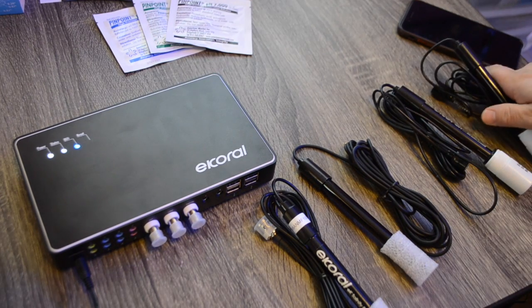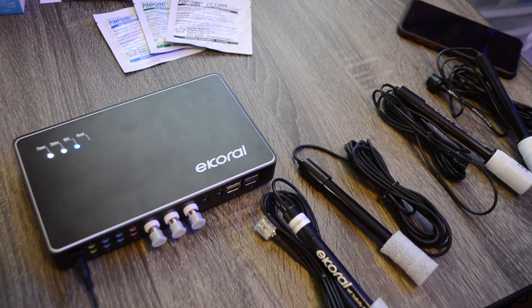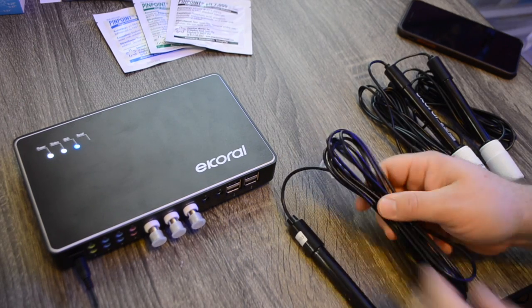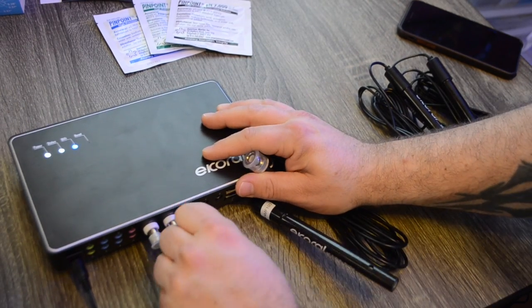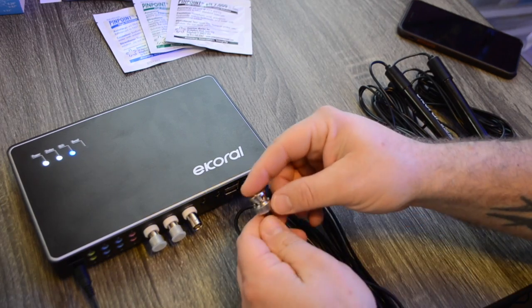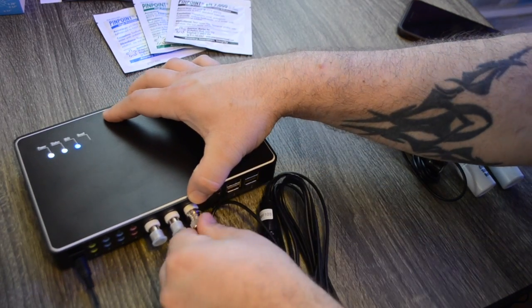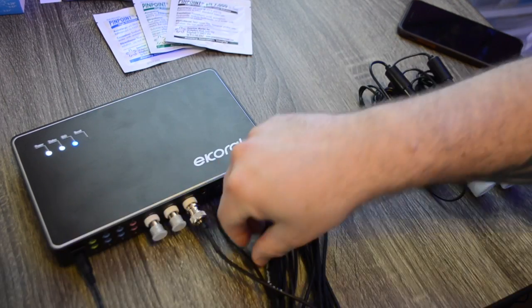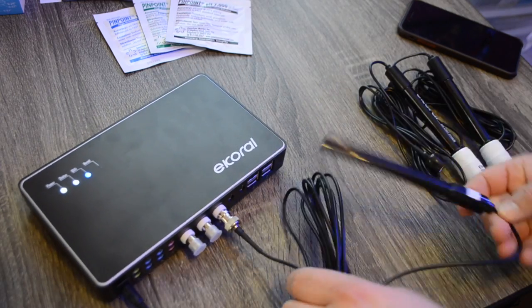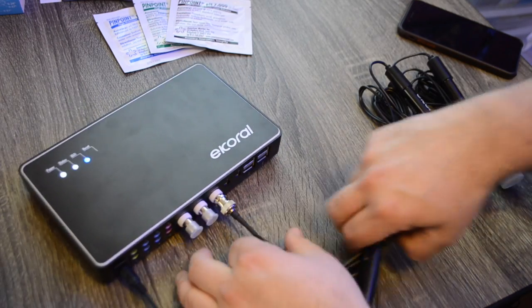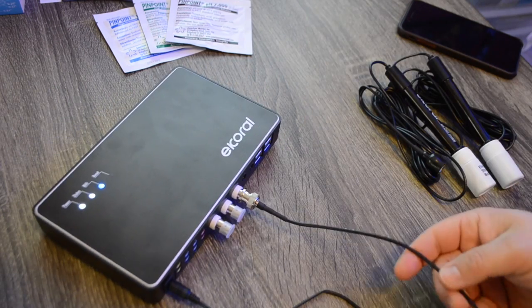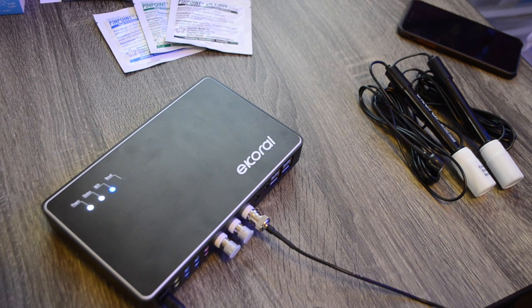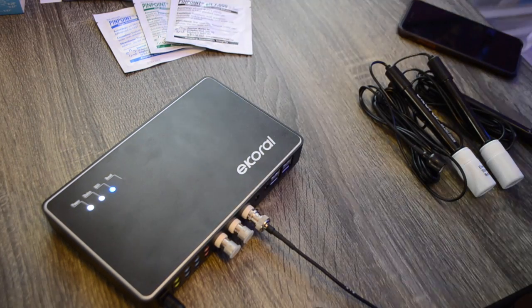When you turn your eKoral on for the very first time, it is going to prompt you to calibrate your probes. But if you don't do it right off the bat, at the very bottom in the right-hand corner, there's 3 dots. If you click on that, it'll bring you to the settings screen. And the second section down, eKoral settings, the first option there is calibration. Once you click on that, it's basically a bunch of tabs at the top. You have pH, salinity, ORP, and water level. And at the bottom of those screens, as you click on those tabs, it says start calibration.